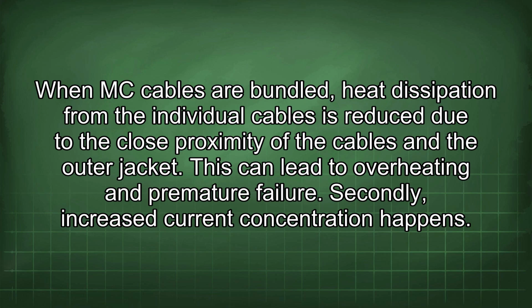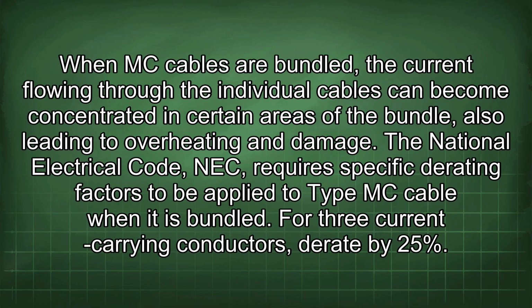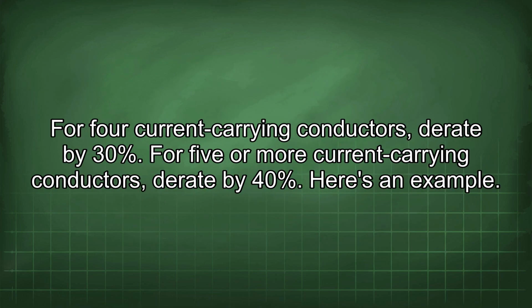Secondly, increased current concentration happens. When MC cables are bundled, the current flowing through the individual cables can become concentrated in certain areas of the bundle, also leading to overheating and damage. The National Electrical Code (NEC) requires specific derating factors to be applied to Type MC cable when it is bundled. For 3 current-carrying conductors, derate by 25%. For 4 current-carrying conductors, derate by 30%. For 5 or more current-carrying conductors, derate by 40%.